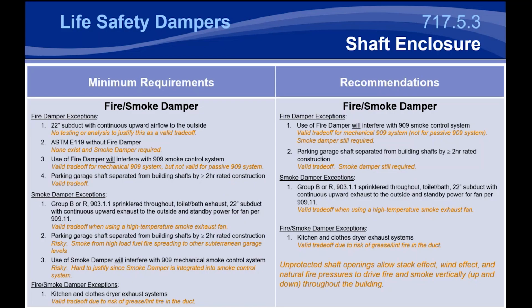To remove the fire damper, it just has to have that subduct, and that's been in code for quite a long time. To remove the smoke damper from the shaft enclosure, it has to be fully sprinklered. Typically, it has to be used with a toilet or bathroom exhaust, and there has to be continuous upward airflow to the outside of the building with standby power. Now that makes sense. If you've got standby power to the fan and that fan is continuously running, and your fan is actually rated a high temperature rating for that smoke exhaust system, you're good. That's how smoke exhaust systems work. So that's a valid trade-off. And removing the smoke damper in those applications certainly makes sense.